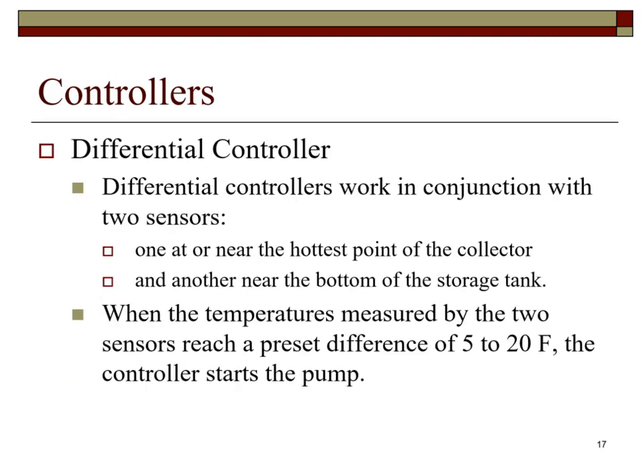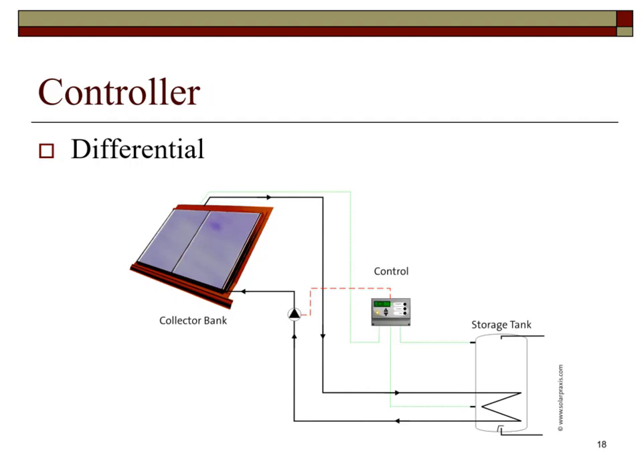The differential temperature controller works in conjunction with 2 temperature sensors. One temperature sensor is near the hottest point on the collector and 1 temperature sensor is at the bottom of the storage tank. As stated here, the temperature difference between the 2 locations can be between 5 to 20 degrees Fahrenheit. When this temperature difference is met, the pump will turn on. This explains the operation of the temperature differential pump controller.